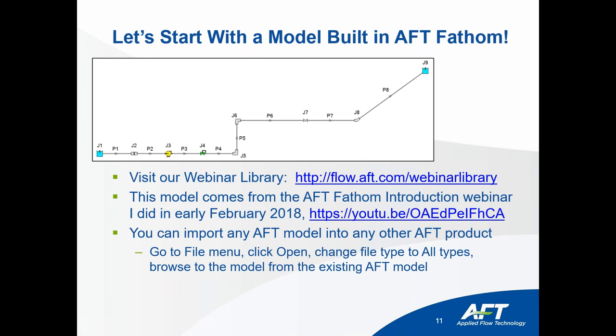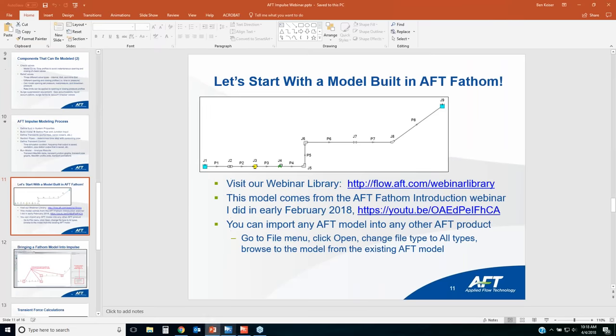This is the model built in the previous webinar — a simple water delivery system delivering 500 gallons per minute of water up a hill, with a 200-foot elevation change. There's a flow control valve, and the piping system was sized so that velocities stay below six feet per second. That is a key thing with water hammer — making your steady-state velocities as low as you can, because the higher your velocities, the larger your pressure surges will be.